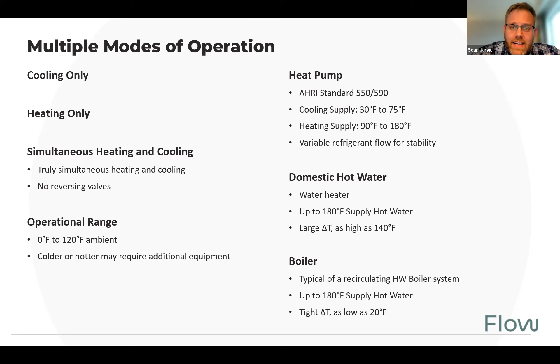Now, where Flow is one of the very few, if not the only competitor playing in the boilers, hot water boiler space, is at low delta T, less than 20 degrees. So for instance, 160 degree return water and 180 degree supply water. Now we're talking true direct, one-for-one hot water boiler replacements. Sure, we switch it to power, but there's things that we can do to really mitigate the need for additional power.